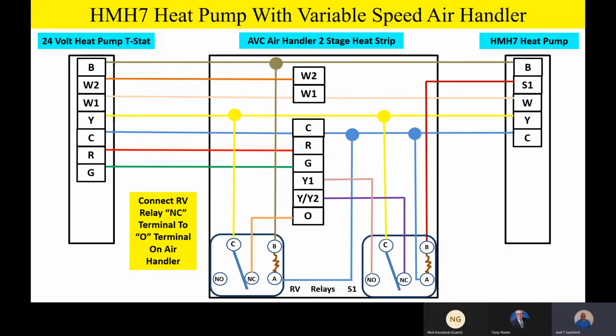So look at this right now. This unit's in the cooling mode of operation right now. We're calling for operation on the Y signal for compressor operation. It's on high speed on the airflow, and the B terminal that goes out to the reversing valve is not energized. So if you take a look at the RV relay, the normally closed contacts right now, we're feeding 24-volt power to the O terminal, and that is correct. So in the cooling mode of operation, the variable speed air handler has to have voltage on O on a heat pump application for some advanced functions.